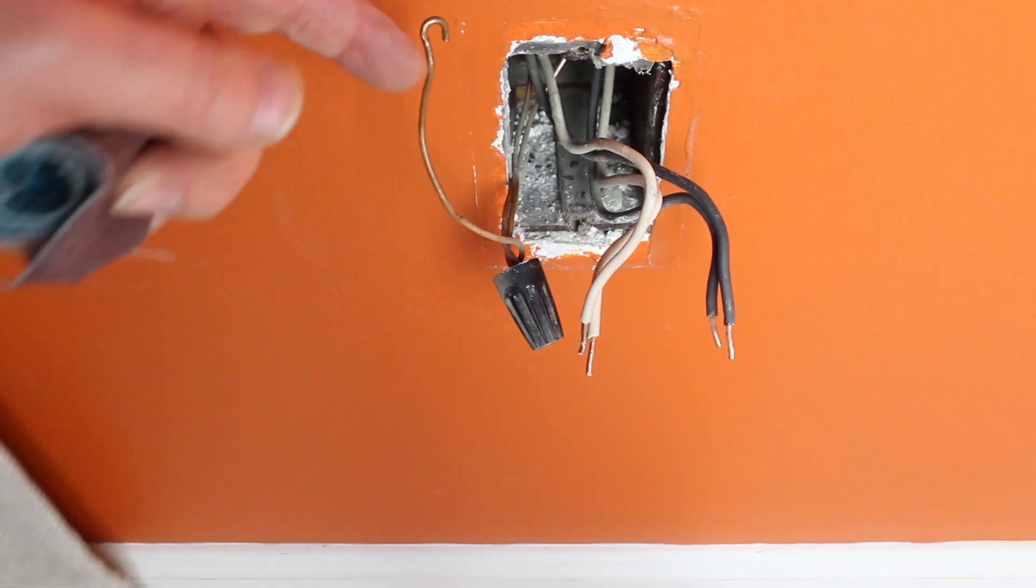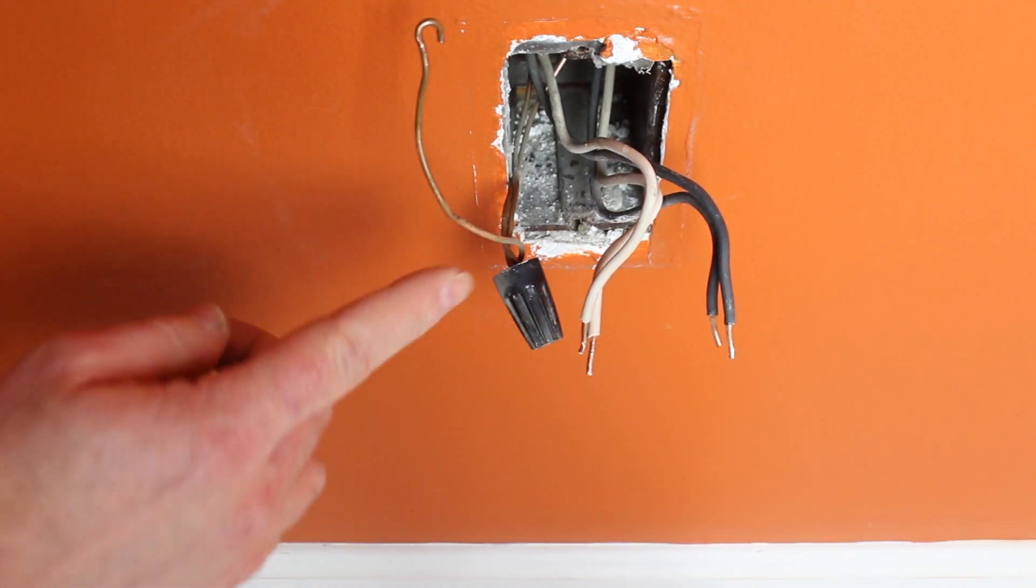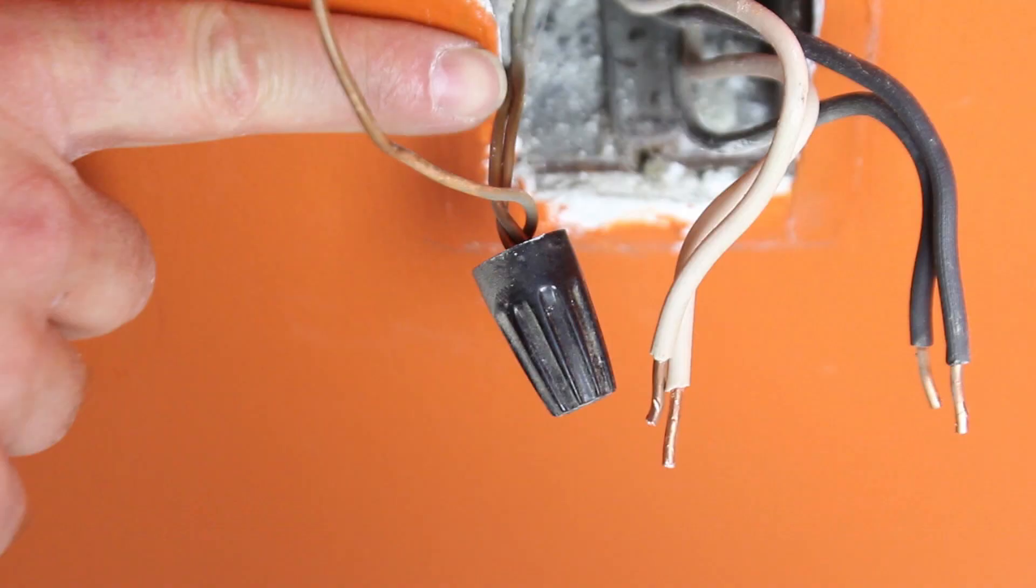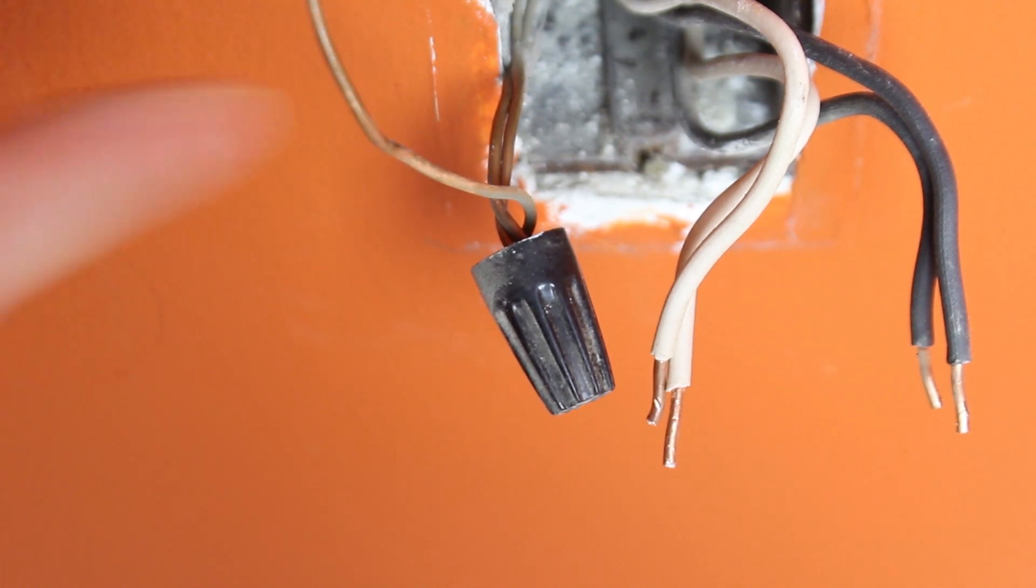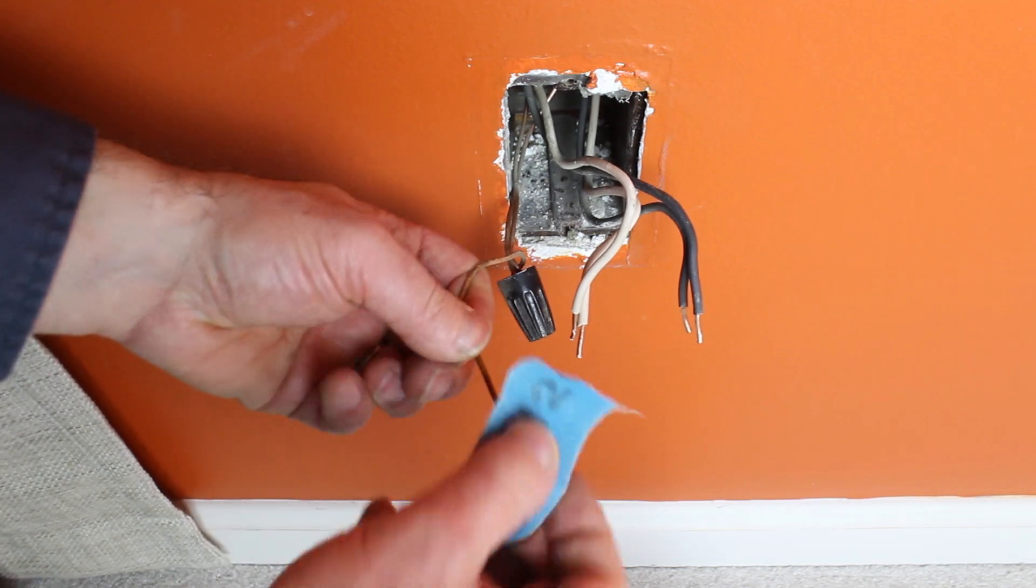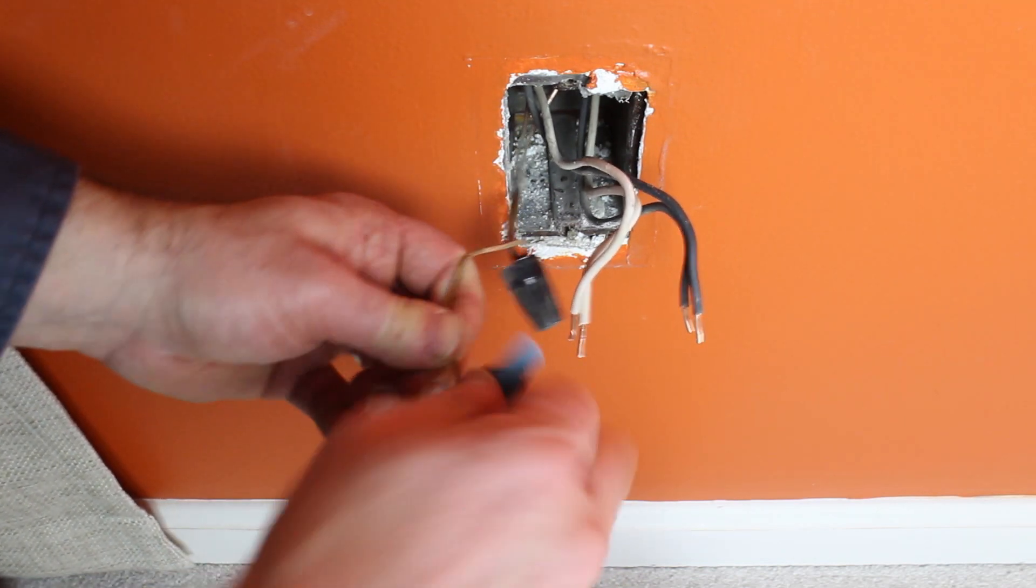I want to show you this. Inside the electrical box, you have your ground wires. They should all be pigtailed together and then have another wire coming out of that pigtail. So there you go. There's the wire nut and there's the pigtail. Take some emery cloth and rub all the bare copper wires with the emery cloth. That way you can be certain that you're going to get great electrical contact with the bare copper wires and that you're going to have a really good contact with your outlet.